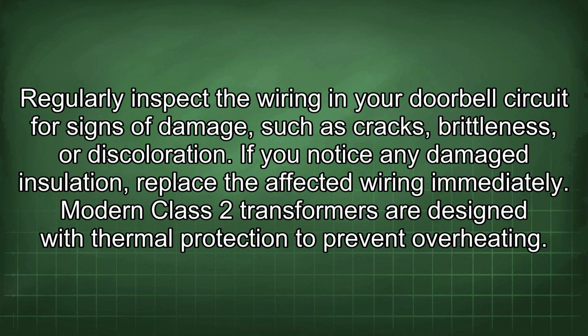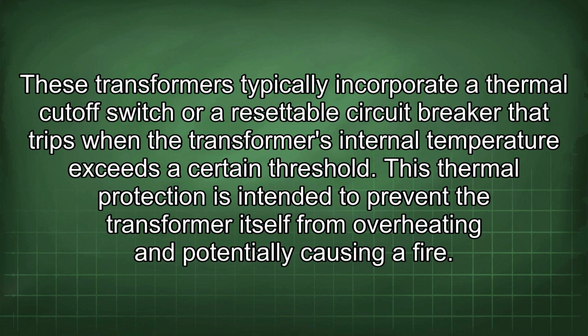Modern Class II transformers are designed with thermal protection to prevent overheating. These transformers typically incorporate a thermal cutoff switch or a resettable circuit breaker that trips when the transformer's internal temperature exceeds a certain threshold. This thermal protection is intended to prevent the transformer itself from overheating and potentially causing a fire.